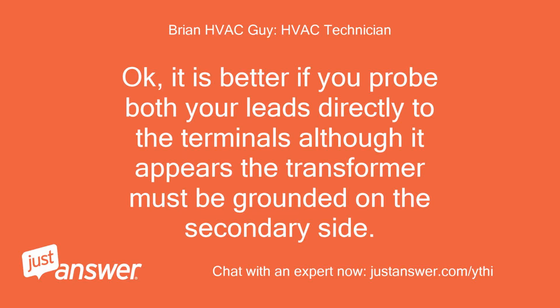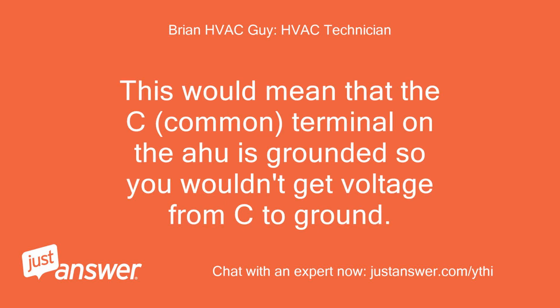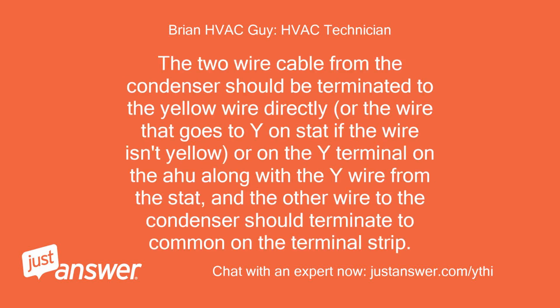Okay, it is better if you probe both your leads directly to the terminals, although it appears the transformer must be grounded on the secondary side. This would mean that the C, common, terminal on the AHU is grounded, so you wouldn't get voltage from C to ground. The 2-wire cable from the condenser should be terminated to the yellow wire directly, or the wire that goes to Y on stat if the wire isn't yellow, or on the Y terminal on the AHU along with the Y wire from the stat, and the other wire to the condenser should terminate to common on the terminal strip.